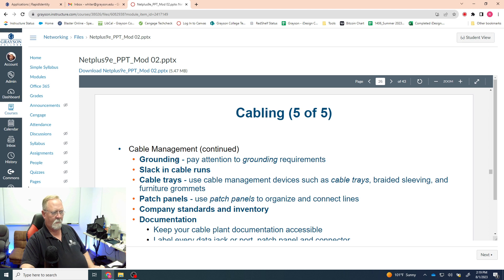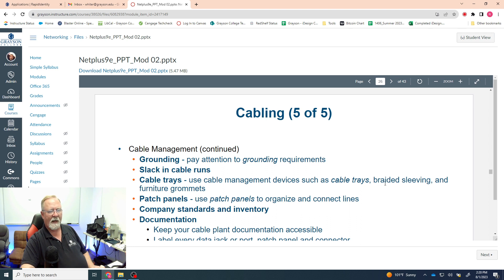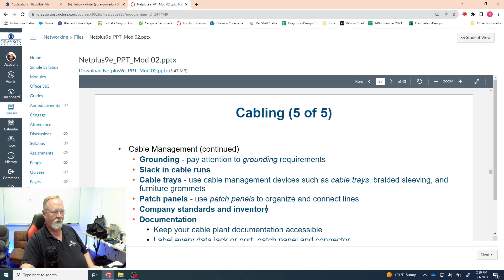If things need to be grounded, make sure they are. Keep slack in your cable runs — do not pull network cable tight, and especially do not pull fiber optic cable tight. Use cable trays — little racks and brackets on the sides of racks that keep your cables in neat bundles. Patch panels organize your connections and connect cables to switches in a neat, orderly fashion.